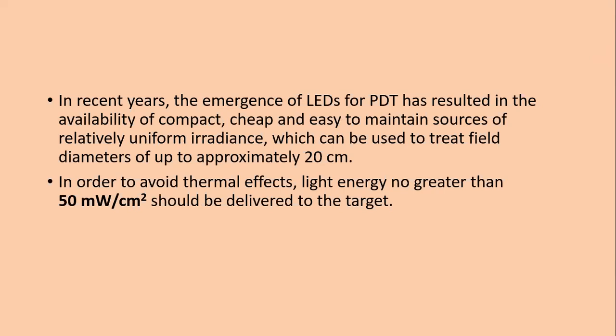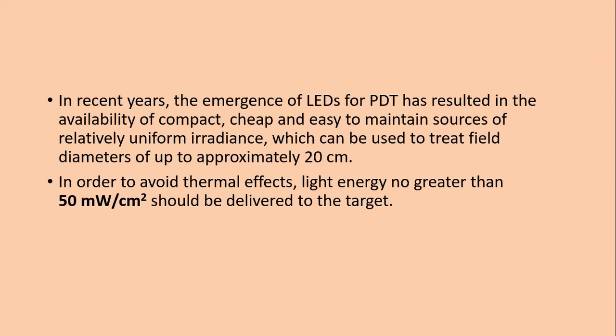In recent years, the emergence of LEDs for PDT has resulted in availability of compact, cheap, and easy-to-maintain sources of relatively uniform irradiance, which can be used to treat field diameters of up to 20 cm. In order to avoid thermal effects, light energy no greater than 50 mW/cm² should be delivered to the target.